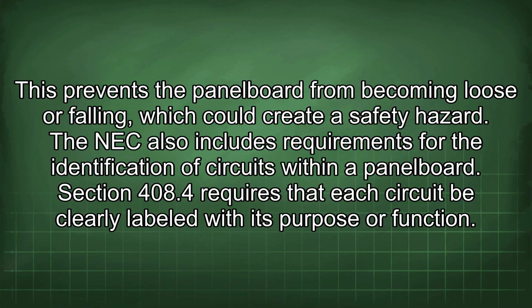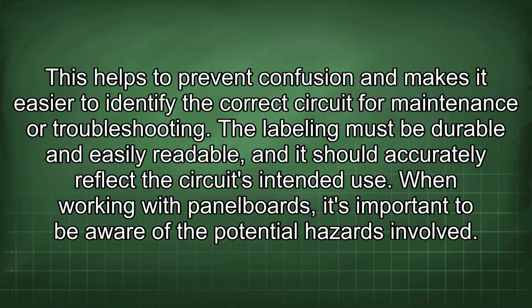The NEC also includes requirements for the identification of circuits within a panelboard. Section 408.4 requires that each circuit be clearly labeled with its purpose or function. This helps to prevent confusion and makes it easier to identify the correct circuit for maintenance or troubleshooting. The labeling must be durable and easily readable, and it should accurately reflect the circuit's intended use.